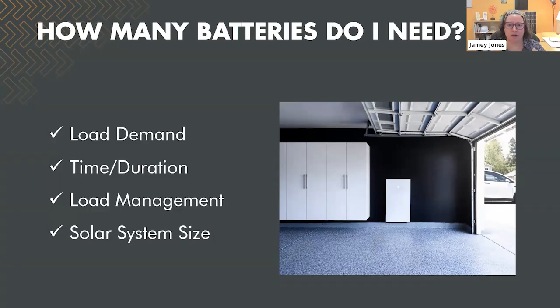And then, what's your largest load? Typically I see large loads being EV chargers, electric ranges, AC units, and electric heating units. So we have to see what your motor loads are, what those breaker ratings are, and how many loads you have in that panel. The largest load in your panel and the number of loads in your panel help us determine the number of batteries you need to get the time, duration, and backup power you need out of your battery system.